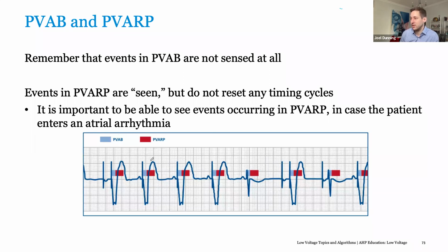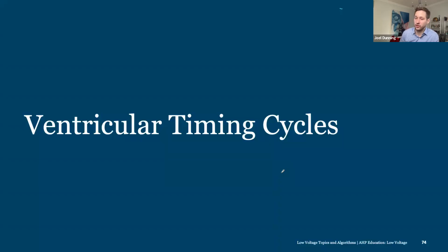So here's a good visualization of PVAB and PVARP. They both will start at the exact same time. So your two clocks both start at the same time. However, your PVAB obviously won't extend as long as your PVARP. So you have your atrial pace event, you have your ventricular pace, which starts the PVAB timer and the PVARP timer. This effectively blanks out any kind of ventricular signal on the atrium with your PVAB. And then this will obscure any possibility of retrograde or inappropriate tracking with the device. Same thing here. If you have an intrinsic ventricular event, when the intrinsic ventricular event is first sensed, that starts your PVAB and your PVARP timers as well. So just a way to visualize it.